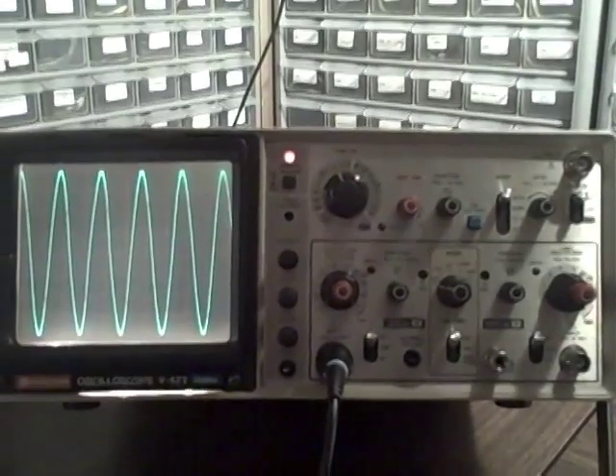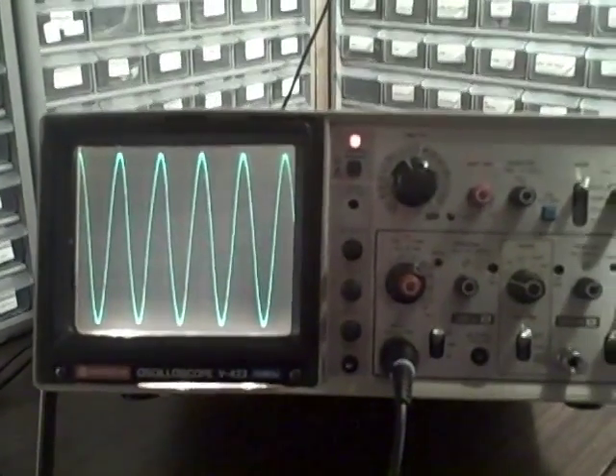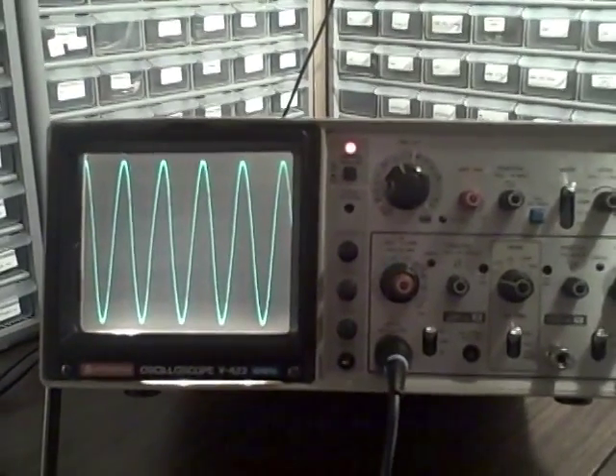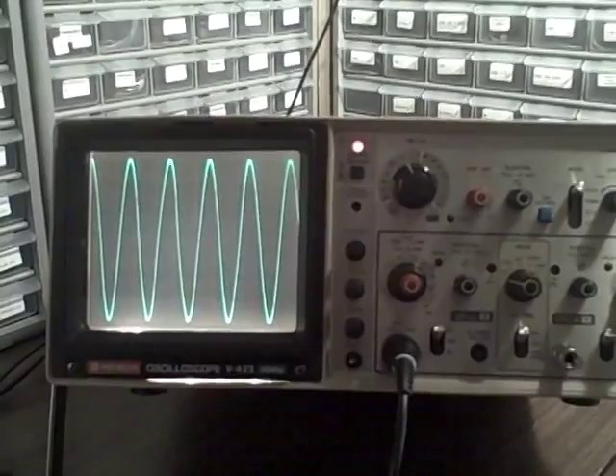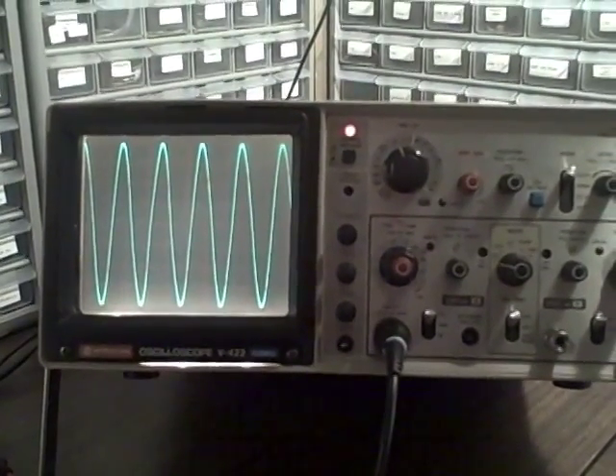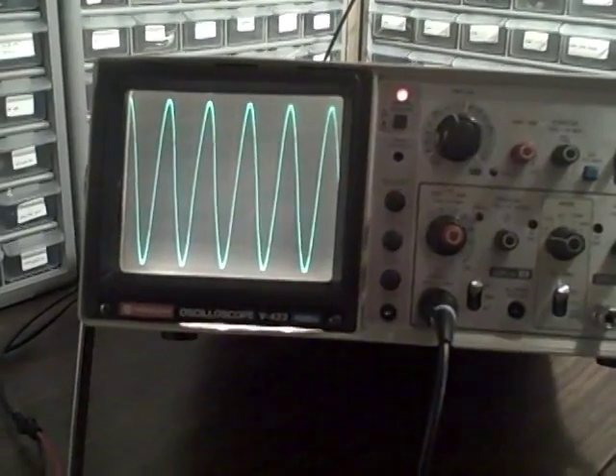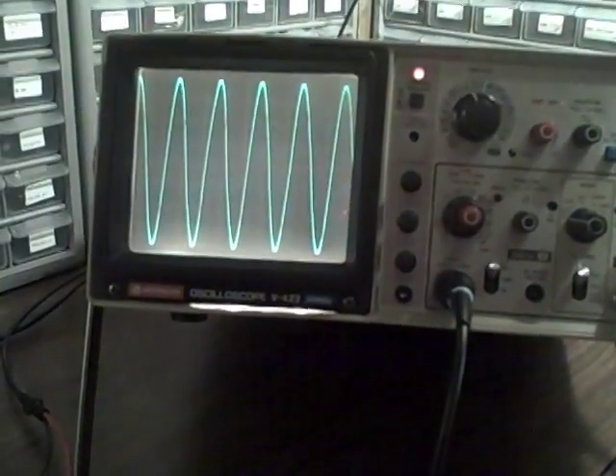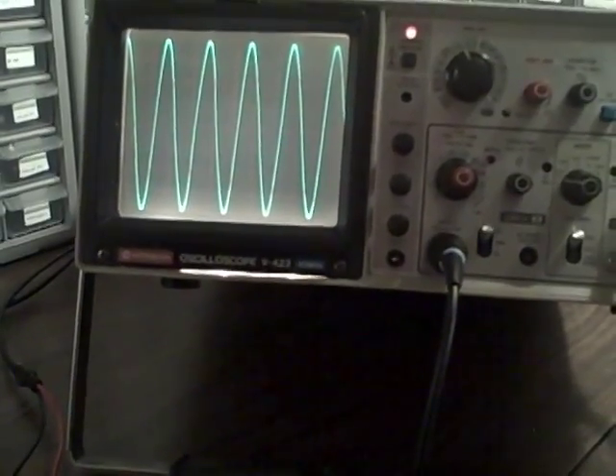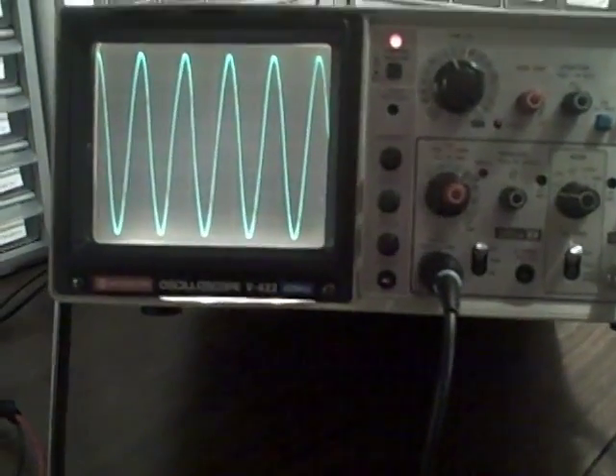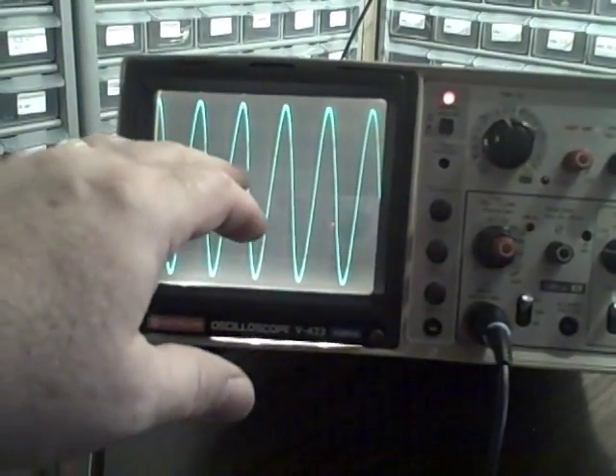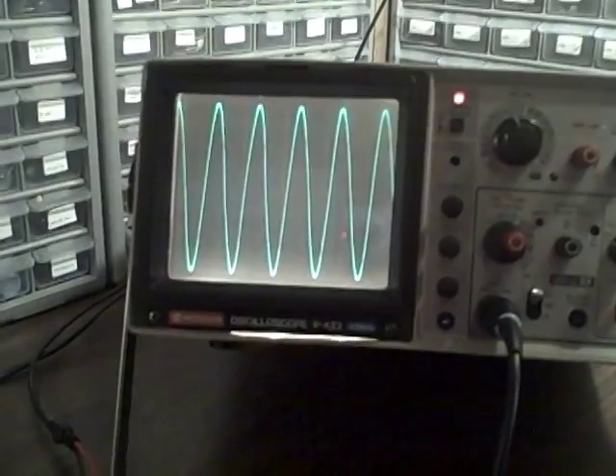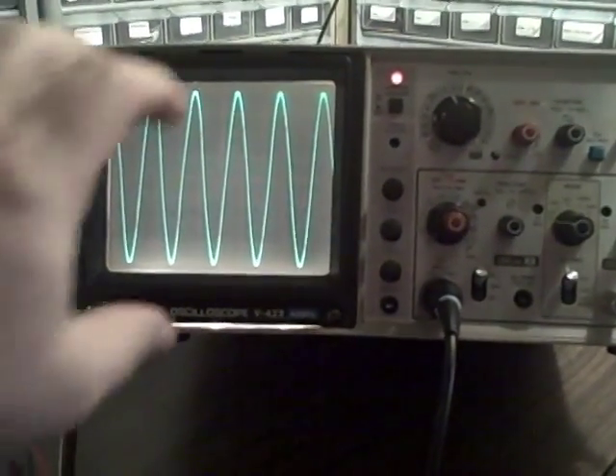Alright, we're connected to our voltage source, and then we're feeding through a probe as a divide by 10 divider, and we are feeding in 20 millivolts. That'd be 200 millivolts on the generator, but then we divide it by 10, so we get 20. We got 20 millivolts AC coming in at a kilohertz here, and on the lowest scale, which is 5 millivolts per division, so we're 5, 10, 15, 20 millivolts peak, and that is what we wanted, and we see that we are spanned exactly plus and minus 4 divisions up and down.